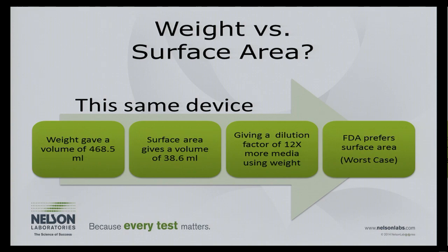If you choose weight, you'll need to justify it to the FDA — and 'it takes less sample' won't be accepted; you need a scientific rationale. The valid exceptions are: powders, absorbent samples like sponges where you can't calculate an accurate surface area, or a device that is very light but has a large surface area where weight could be considered worst case. Otherwise, everything should be done by surface area.